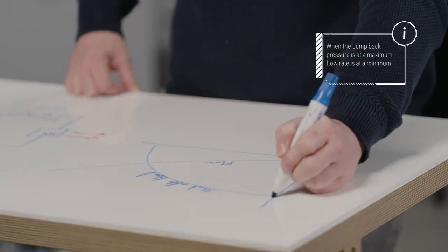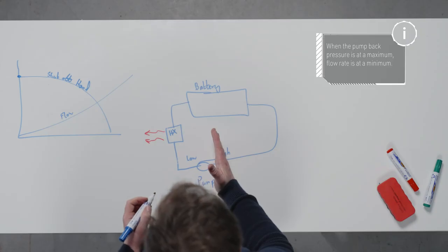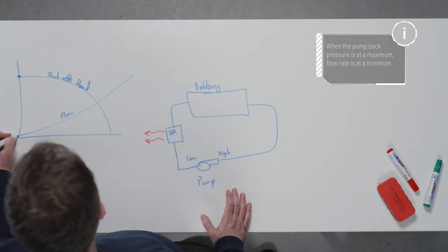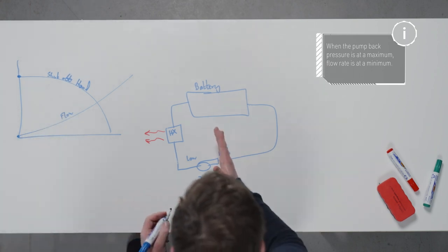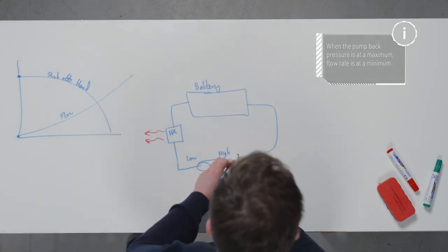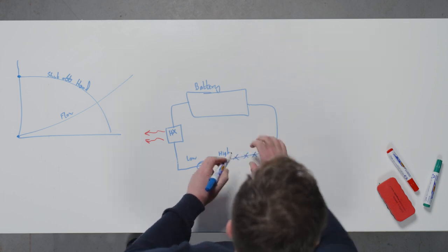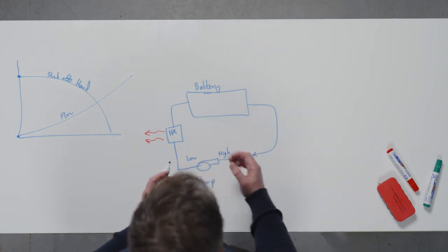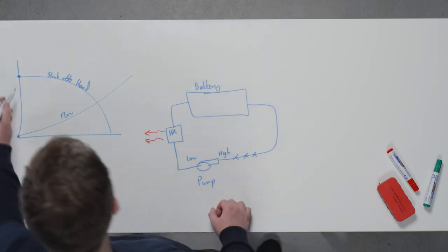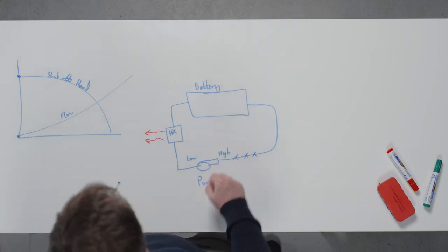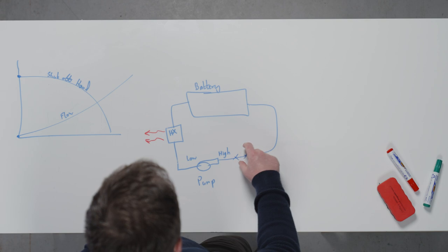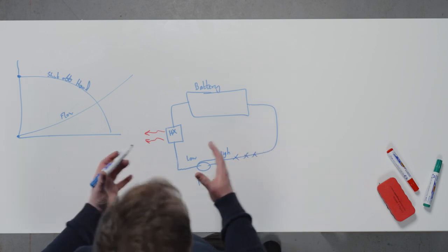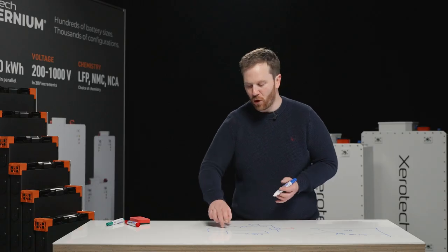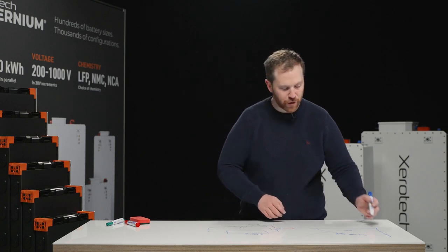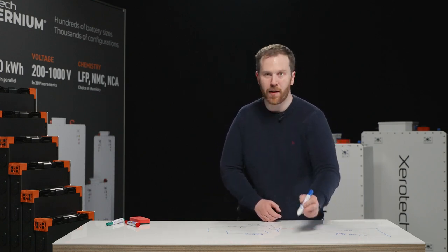What this curve tells us is basically when the pump back pressure is at a maximum, flow is at a minimum. So basically when you block off the pump or have as much constrictions as possible on this loop and many devices, the back pressure fighting the flow of water will be at a maximum and flow will be at a minimum. So what you're trying to do is to not have obstructions or back pressure or things obstructing that flow in your loop, and you want to develop the highest flow that you possibly can.